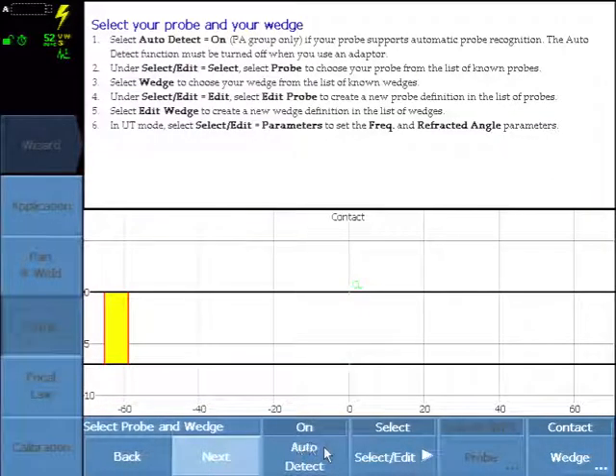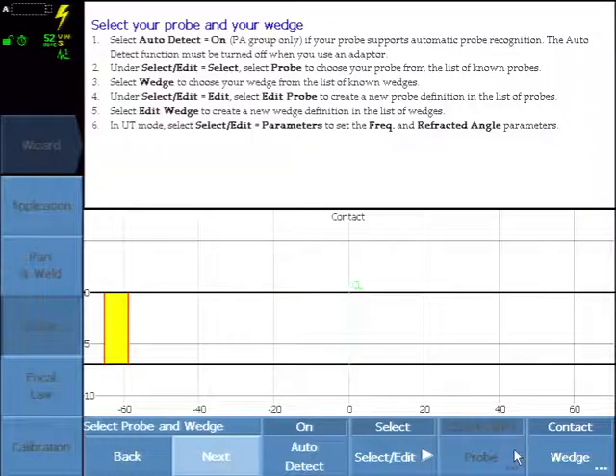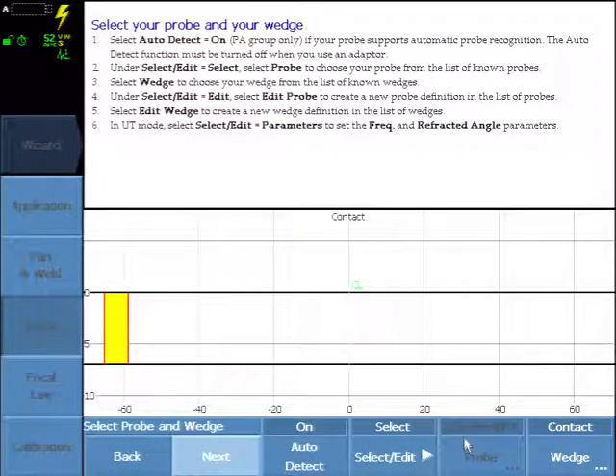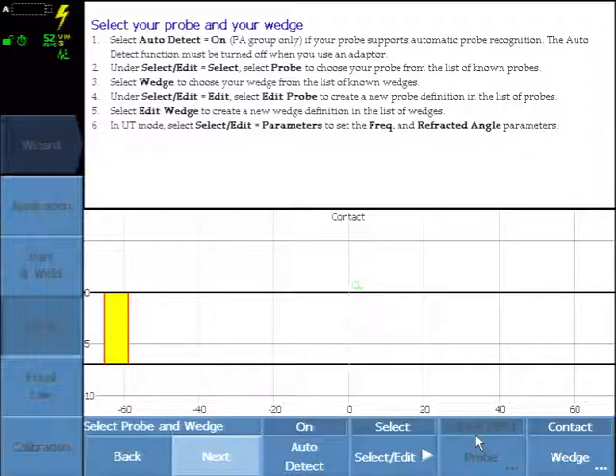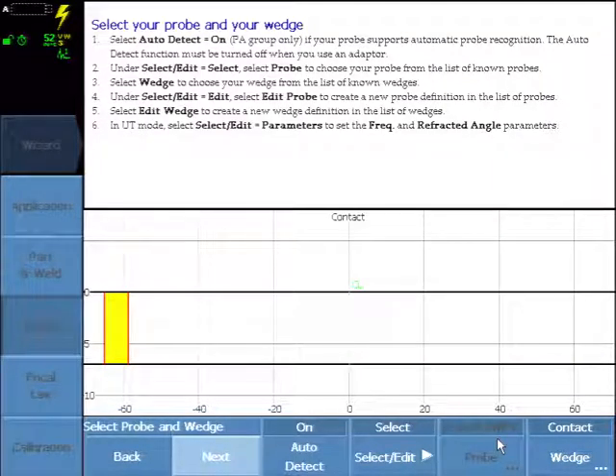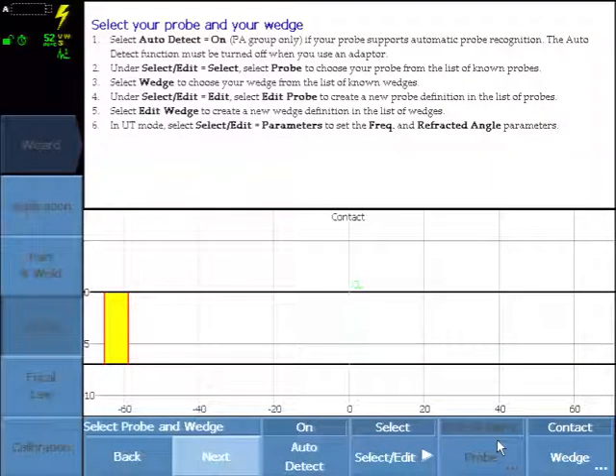With Auto Detect On, the probe parameters are automatically detected. This is a 3.5 MHz linear array, 64 elements and designed for near wall inspection to be used with the roller form.